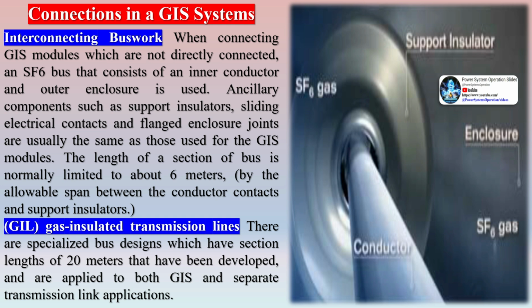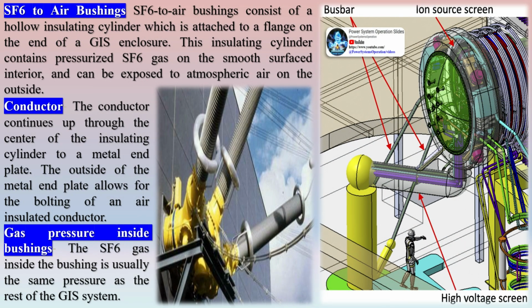When connecting GIS modules which are not directly connected, an SF6 bus that consists of an inner conductor and outer enclosure is used. Ancillary components such as support insulators, sliding electrical contacts and flanged enclosure joints are usually the same as those used for the GIS modules. The length of a section of bus is normally limited to about 6 meters by the allowable span between the conductor contacts and support insulators. Gas insulated transmission lines: there are specialized bus designs which have section lengths of 20 meters that have been developed and are applied to both GIS and separate transmission link applications.